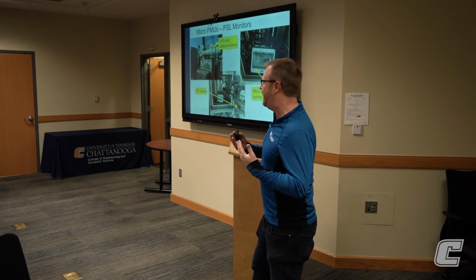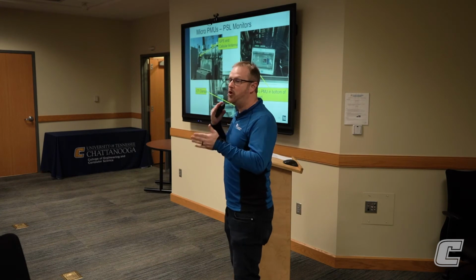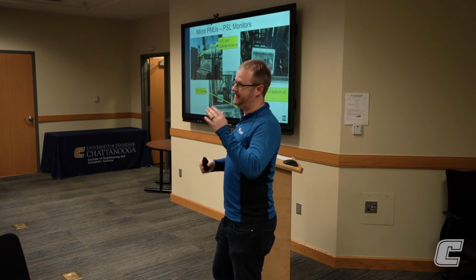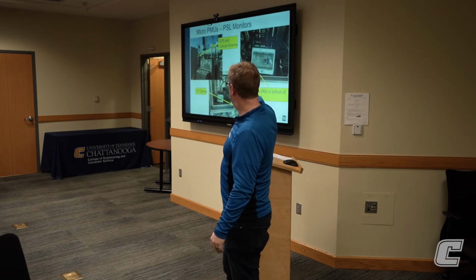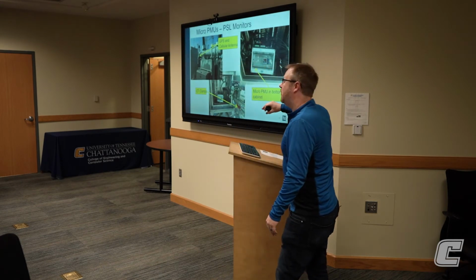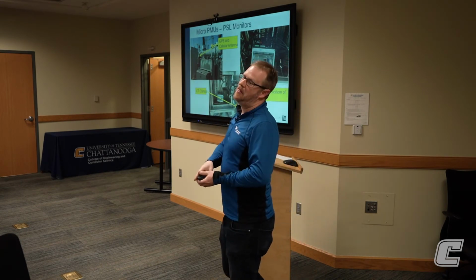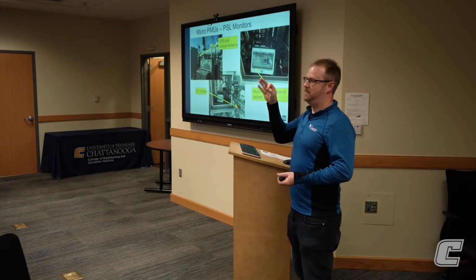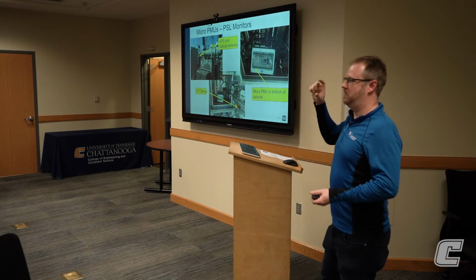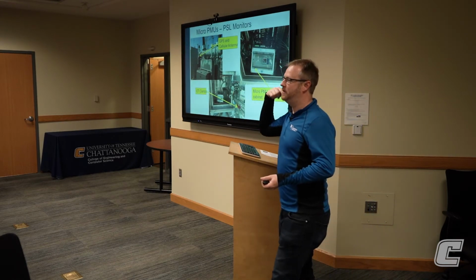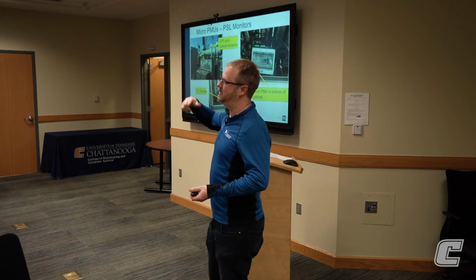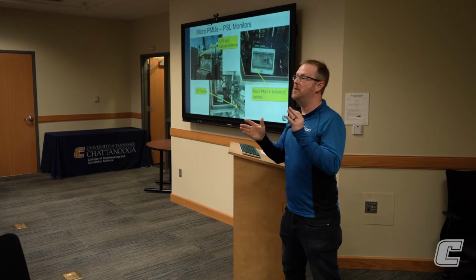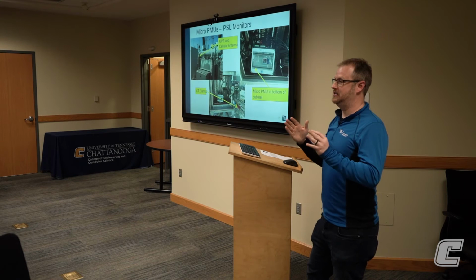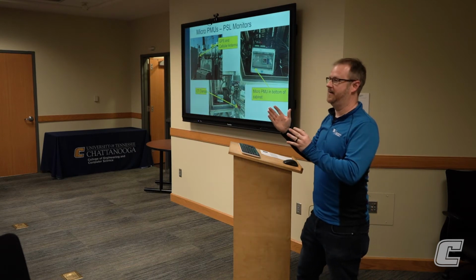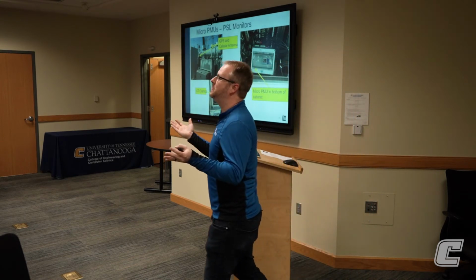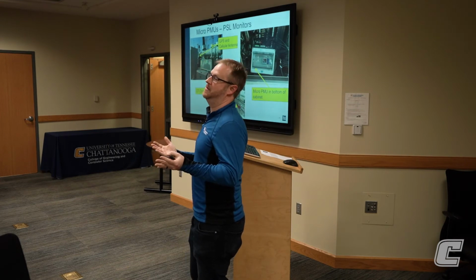But we didn't have the high resolution data from Scada to show who was flinching first. Once we got this micro PMU in, we could actually see that their exciter was moving first, their megavars were moving out of the unit first, and then our voltage was following whatever the exciter was doing. So we could show they were moving first, and then our system grid voltage was following, proving there was something going on with their exciter.